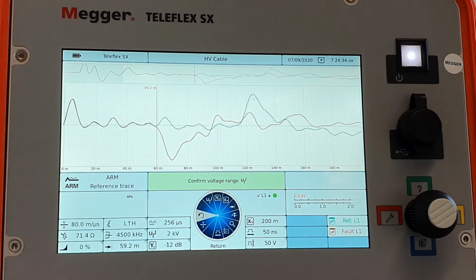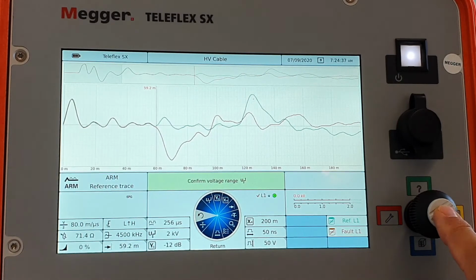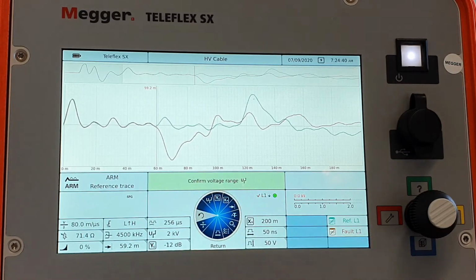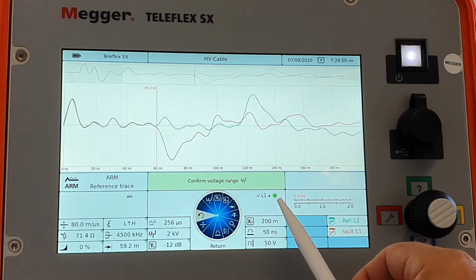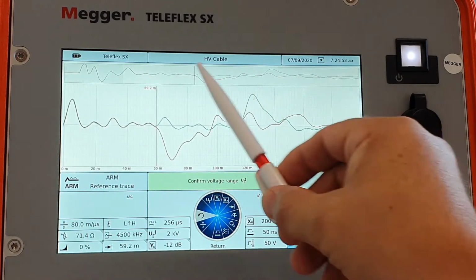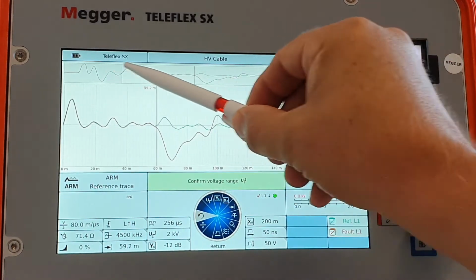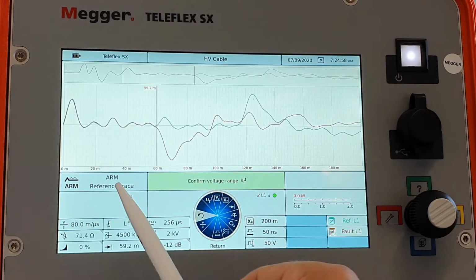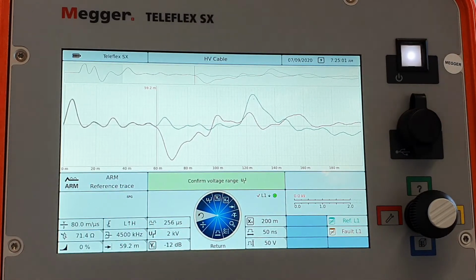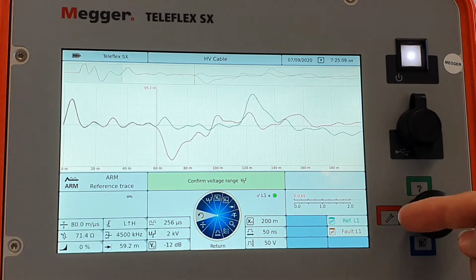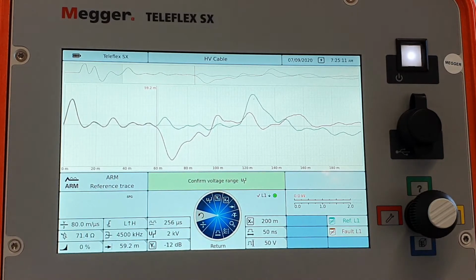The whole fault locating system is controlled over this one button, and this is our main control panel. Here we see the most important information. We see which phase we're connected to, if we apply voltage or not. Right now we are grounded. We see our measurement window with an overview over the whole cable, and we see which method we're using. All is controlled with this single button, and we have 4 ways of clicking up, down, left or right, which gives us the quick access menus.